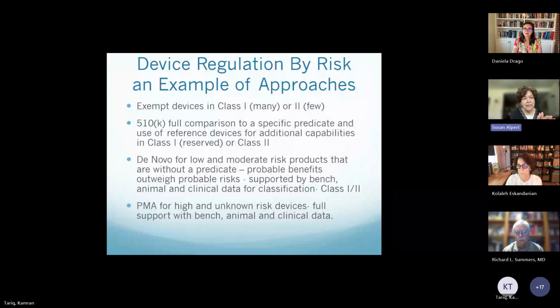So on the device side, there are different regulatory tools depending on the risk of the specific product. There are some products that are such low risk that you have to follow the rules and develop all the data, but FDA doesn't need to see that data unless there's a problem. So even if you're an exempt product, meaning FDA doesn't need to give you permission to market, and that's for the lowest risk products and some moderate risk products which FDA has decided they don't need to see before they go to market, you have to have all of that information. You have to have all the documentation. Otherwise, you have to make some form of submission and get FDA's approval for entering the market.